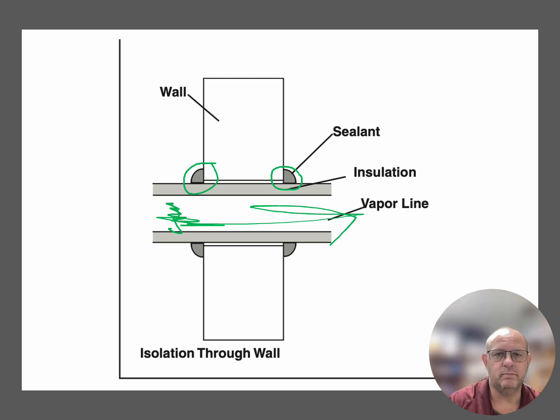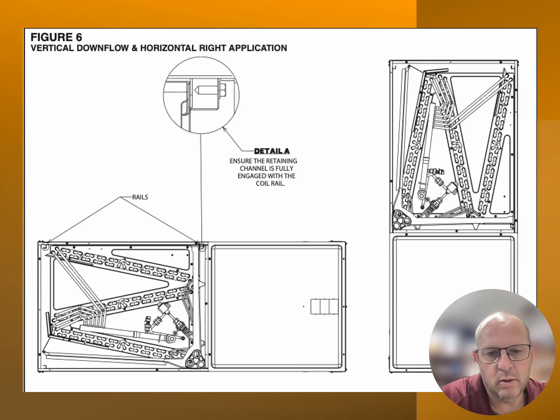Most of our units can be multi-positional. This is an air handler for a Rheem. We're looking at it, and we've got to ensure the retaining channel is fully engaged in the coil rail, such as these guys up in here. And it's going to hold that coil in place. Read the manual and find out how you're going to flip these coils.